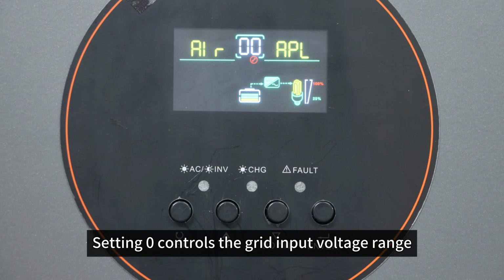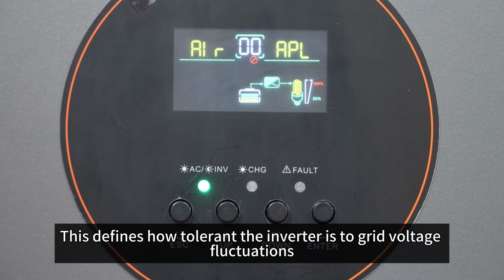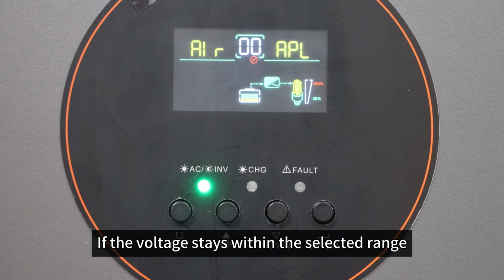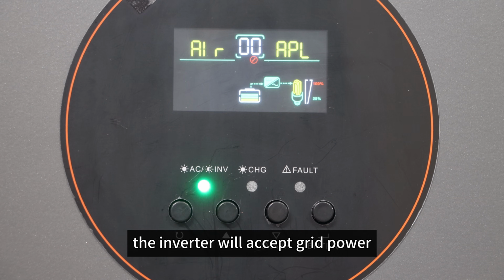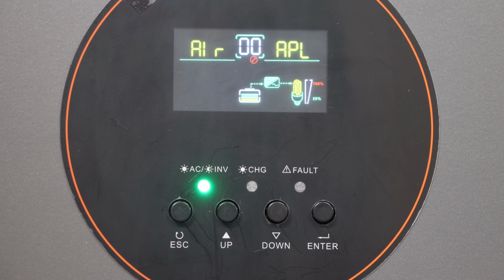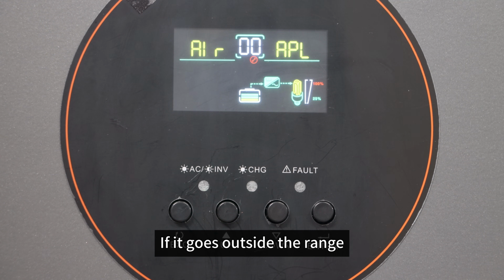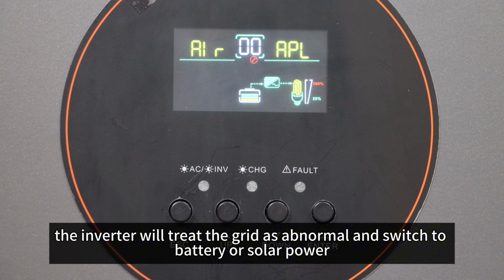Setting 0 controls the grid input voltage range. This defines how tolerant the inverter is to grid voltage fluctuations. If the voltage stays within the selected range, the inverter will accept grid power. If it goes outside the range, the inverter will treat the grid as abnormal and switch to battery or solar power.